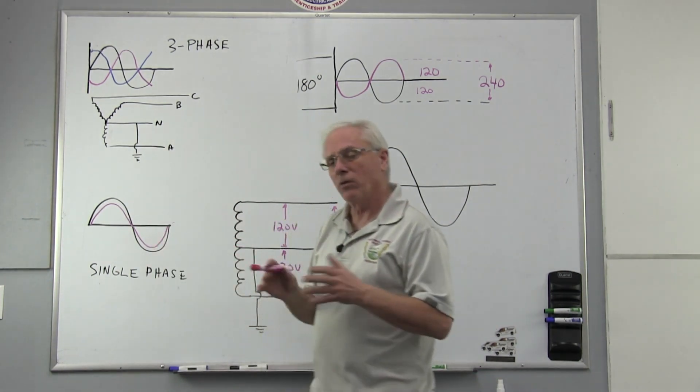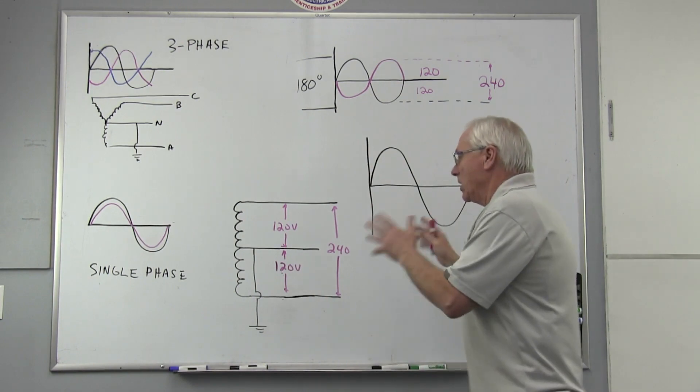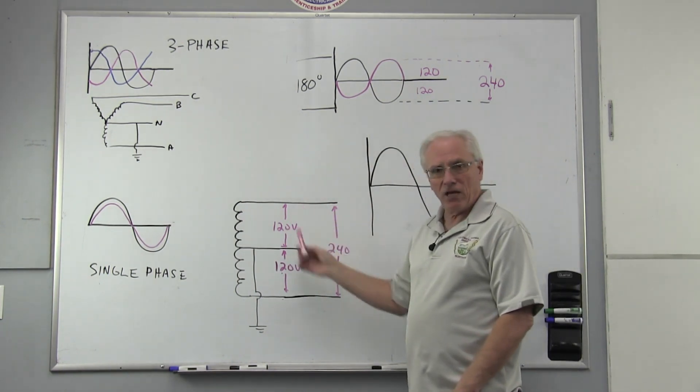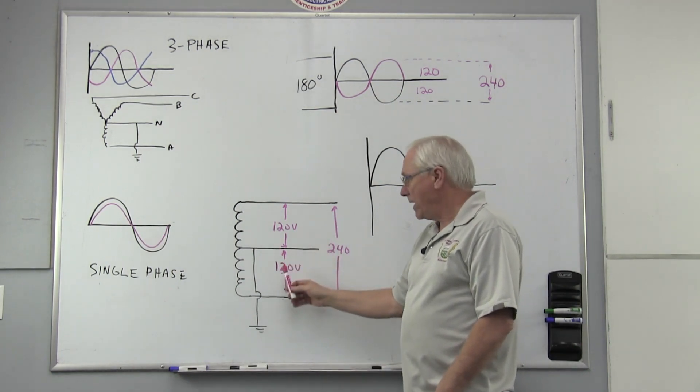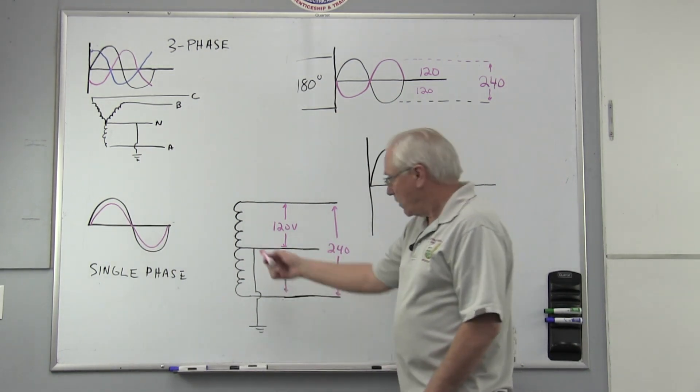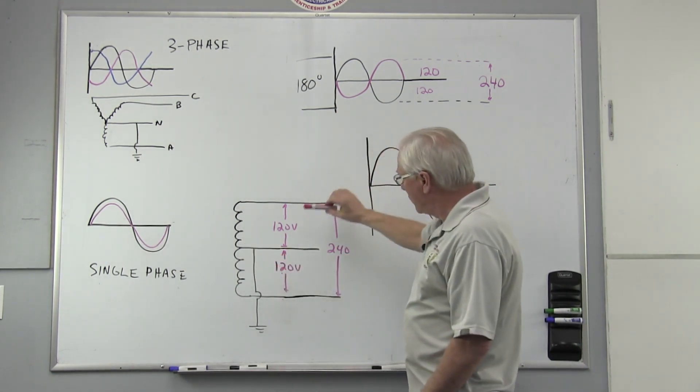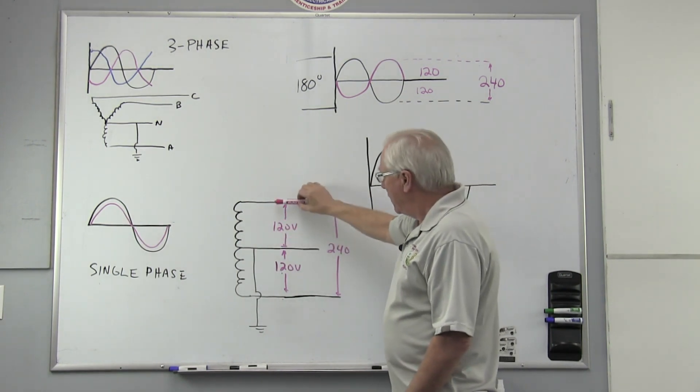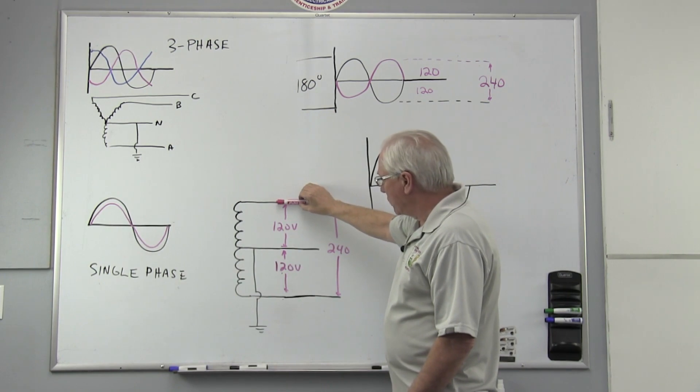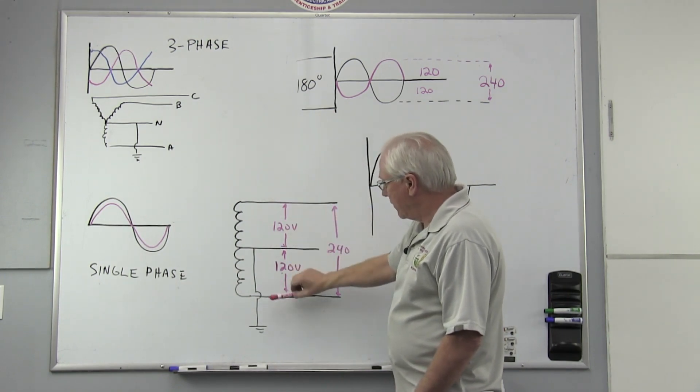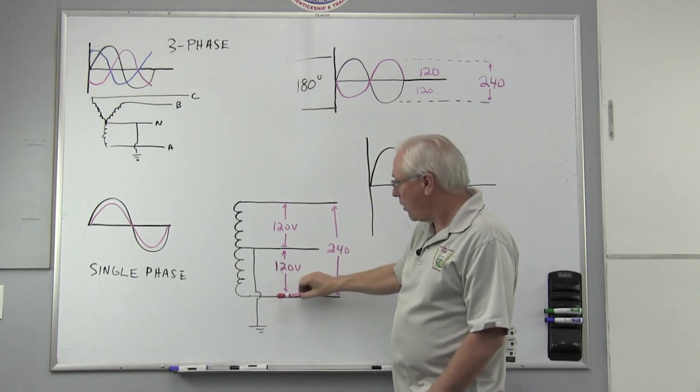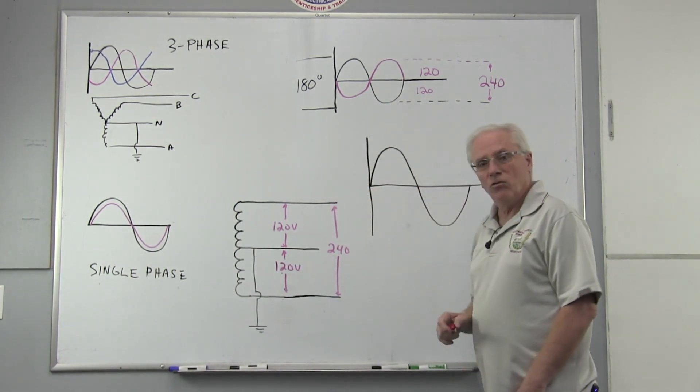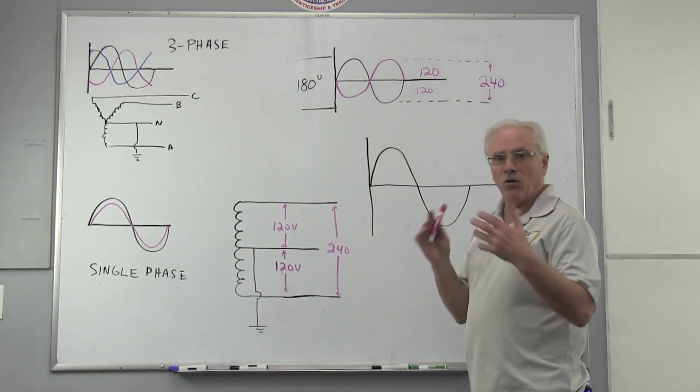A 120 volt, 240 volt system is usually drawn like this, and this is correct. It's one transformer and one set of windings, and they center tap it. Between the neutral conductor and one side of the transformer you get 120 volts, and the neutral and the other side you get 120 volts. Also between the two end windings you get 240 volts. It's a single phase impulse.